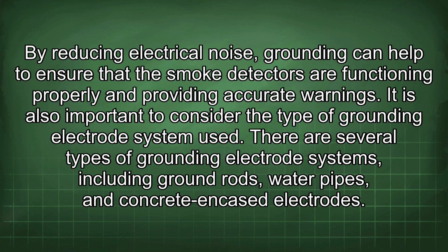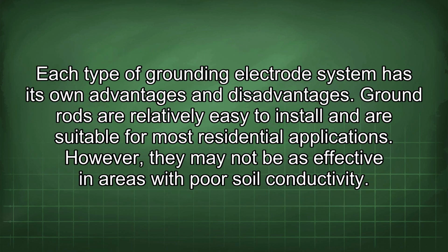It is also important to consider the type of grounding electrode system used. There are several types of grounding electrode systems, including ground rods, water pipes, and concrete-encased electrodes. Each type of grounding electrode system has its own advantages and disadvantages. Ground rods are relatively easy to install and are suitable for most residential applications. However, they may not be as effective in areas with poor soil conductivity.